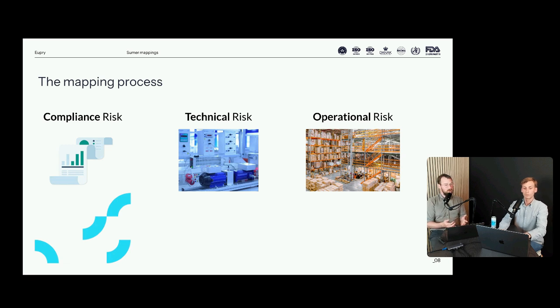So that's basically the underlying risk. And for the grid selection, the loggers that we normally place in corners and in the center and in 3 different heights, depths, and lengths, as I mentioned, that's basically because we have a homogeneity risk and a stability risk, one might say. But we also do need to apply risks that are based on, as I mentioned, HVAC systems, blowout air, doors, windows, gates, forklift chargers, all these different things. You need to consider all the different types of risk.